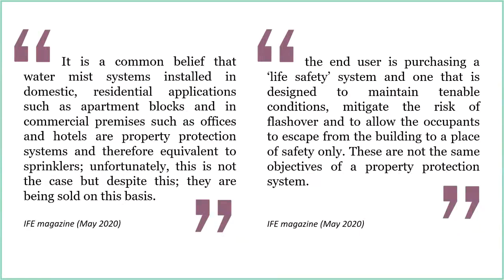Yes, we can get sprinkler systems that are for both property protection and life safety, but mist systems, correct me if I'm wrong, seem to be purely for life safety purposes. That means they're going to be good at holding the fire back and providing adequate time for evacuation. But if you want that system to actually protect the property, to suppress the fire, to save your stock, mist systems just aren't designed to do that. In my opinion, they're not powerful enough in terms of the penetration of water into the items on fire - I'm talking about large category A fires here.